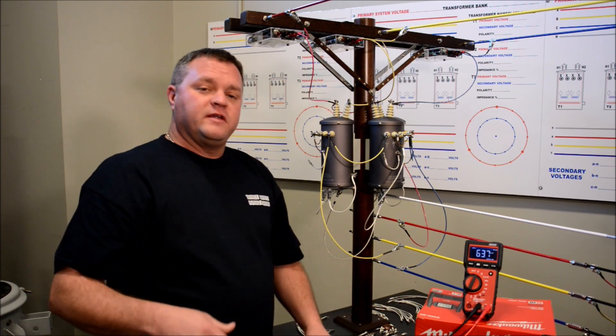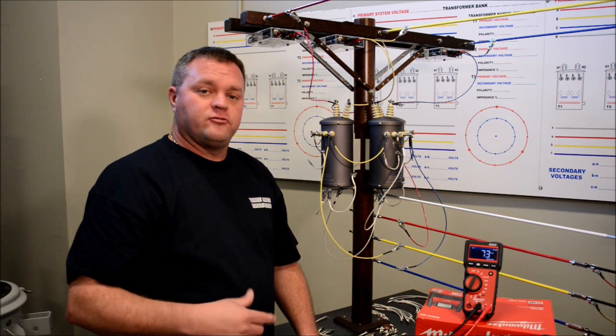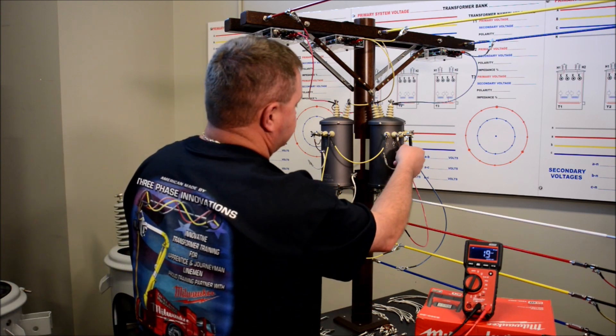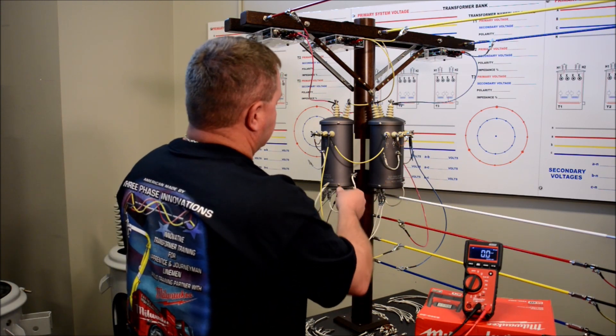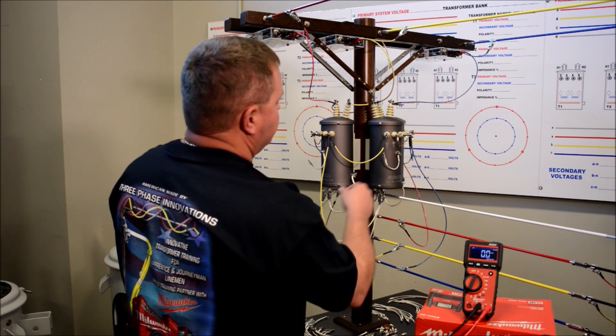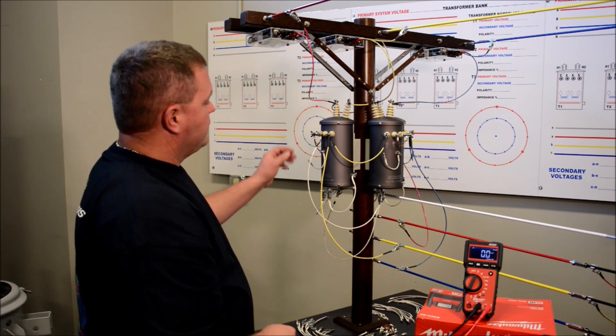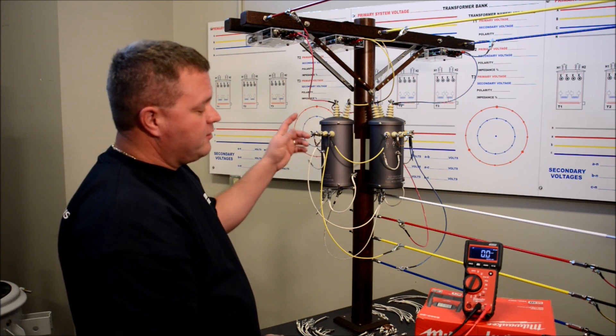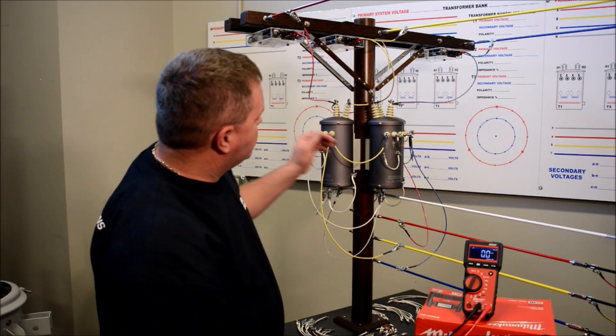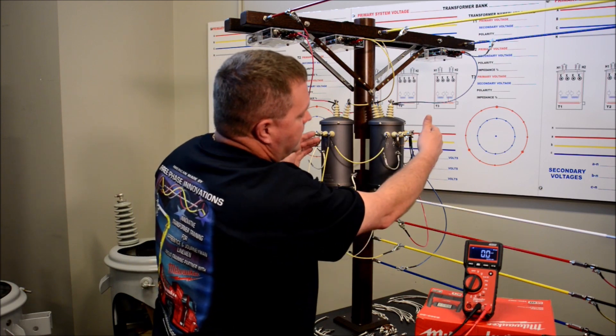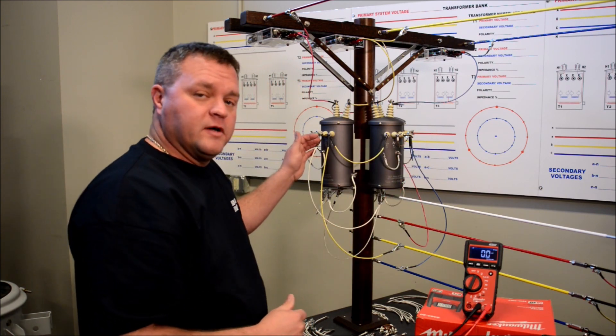But right now we're going to de-energize it, move the ground and show you how that high leg can be easily shifted. Right now we're taking it from B to C. We're going to take it over here between A and B. So A and B to ground we're going to be 120. C, because we're traveling three coils away, it's going to put us at 208.